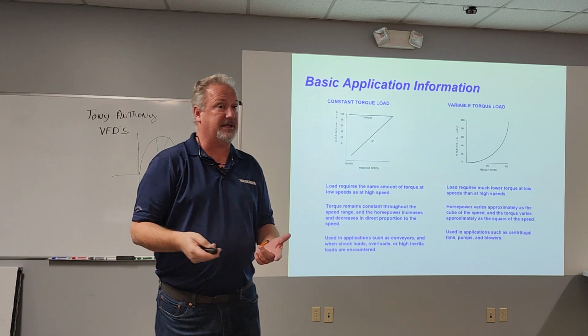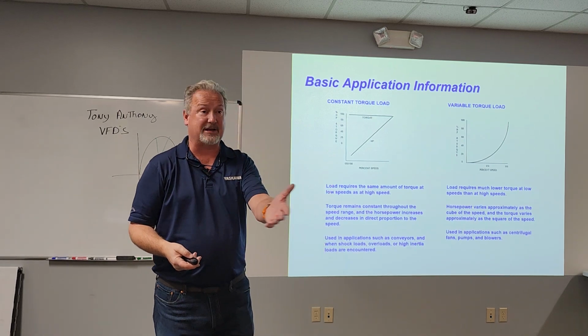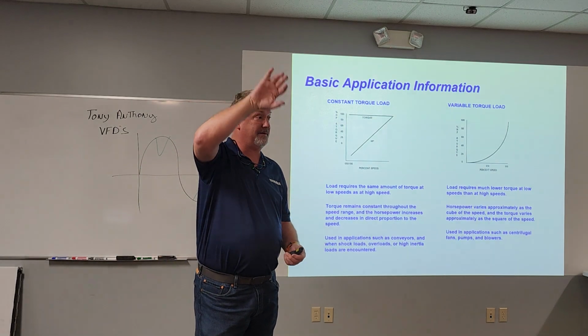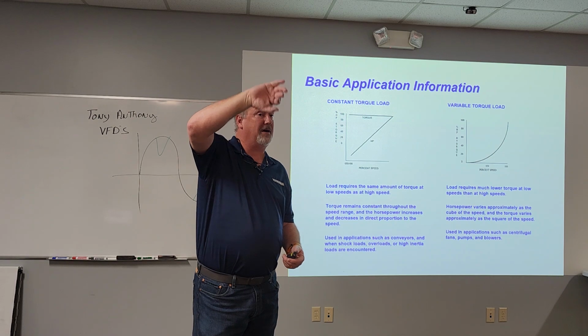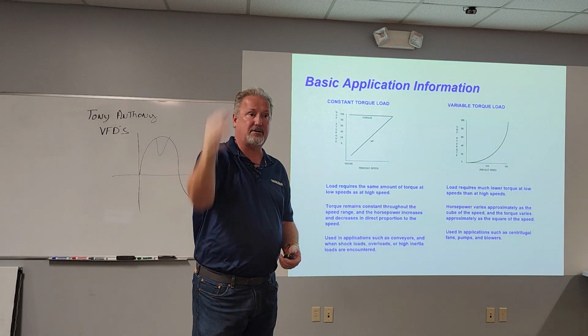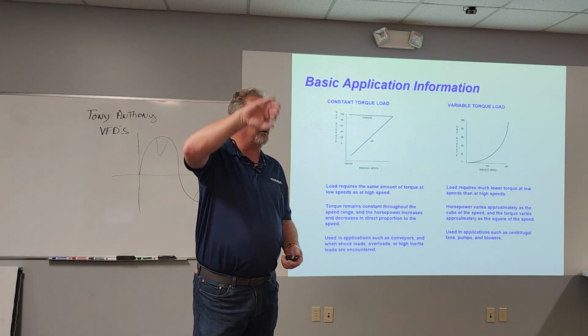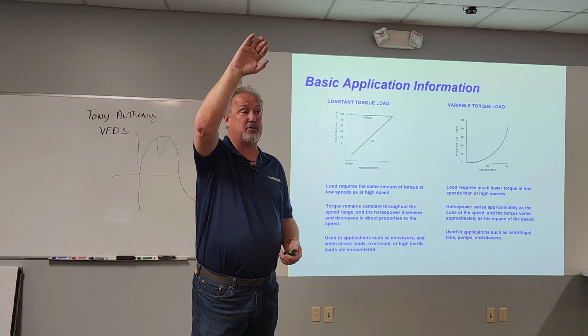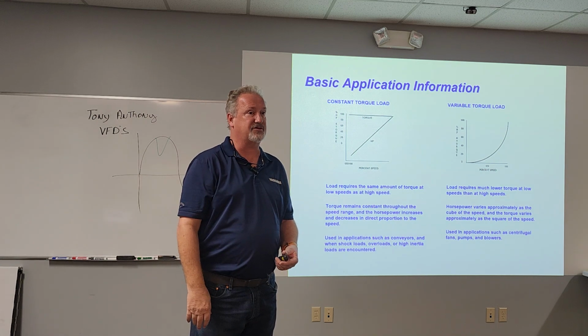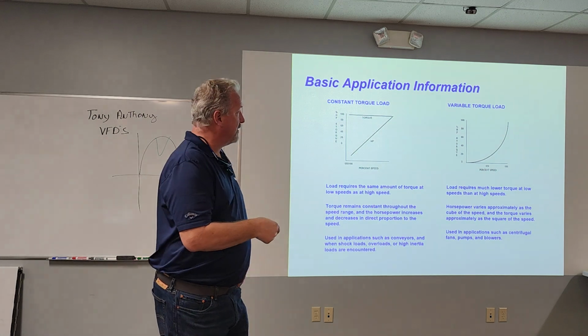And you've got to watch the torque curves. A lot of motors, and even the fans, have torque curves. Somewhere above 60 hertz, at some point, you just lose it. So you might get to 80, and then at 82 you have no flow. It just drops off. So you've got to be very careful when you're going above 60.